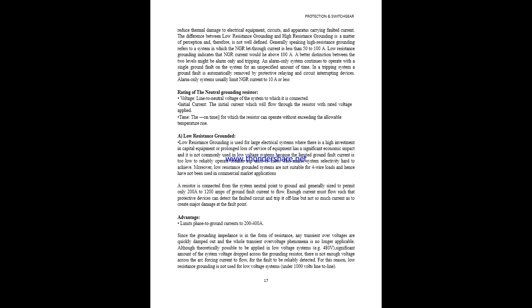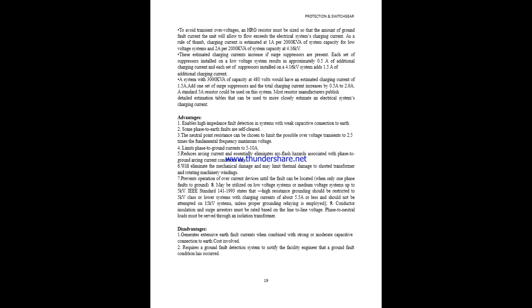Low resistance grounding, its main advantage is that it can limit currents up to 200 to 400 amperes. And high resistance grounding is mainly capable of limiting the current to 5 to 10 amperes, or 1 ampere per 2000 kVA system to 2 amperes per 2000 kVA system, which has a capacity of 4.16 kilovolt.